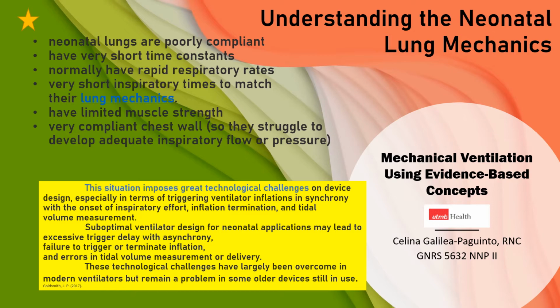They have limited muscle strength and a very compliant chest wall, so they struggle to develop adequate inspiratory flow and pressure. This situation imposes great technological challenges on device design, especially in terms of triggering ventilator inflations in synchrony with the onset of inspiratory effort, inflation termination, and tidal volume measurement. Suboptimal ventilator design for neonatal applications may lead to excessive trigger delay with asynchrony, or failure to trigger or terminate inflation, and errors in tidal volume measurement or delivery. These technological challenges have largely been overcome in modern ventilators but remain a problem in some older devices still in use. That's why it's important to have a clinical eye to be watchful of neonatal lung mechanics.